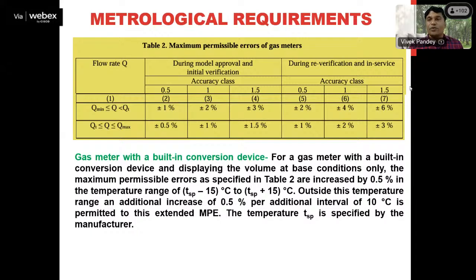That is the variation of these MPEs based upon the temperature of the gas. Because unlike other measuring instruments specified in our rule, in the case of gas meters, if the gas temperature is varying, it can change the quantity of gas, or you can say the measurement result, considerably based upon variation in temperature. So depending upon that, the tolerance level is also changed.